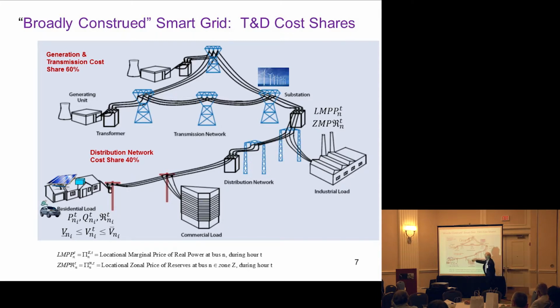Down here, we don't. Although this transformer may have a rated capacity, during certain hours we may load the transformer beyond its rated capacity. The transformer doesn't fail -- occasionally it does. I've seen transformers burst into flames, in Manhattan. It doesn't happen too often. But usually what happens when you overload them is that their life starts declining very, very fast.